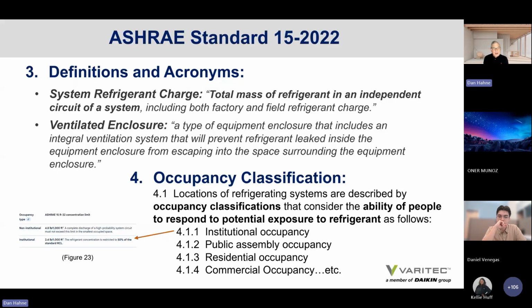And then there's the definition of a ventilated enclosure, a type of equipment enclosure that includes an integral ventilation system that will prevent refrigerant leaked inside the equipment enclosure from escaping into the space surrounding the equipment. Section 4 of Standard 15 has occupancy classification distinctions. And this does make a difference in how the releasable refrigerant charge is calculated. You will notice that institutions have 50% lower refrigerant concentration level than that prescribed for the refrigerant in Standard 34. So if variable refrigerant is being designed for a school or a university or maybe even a hospital, we have to look into those refrigerant concentration limits to make sure that the institutional requirements are met.